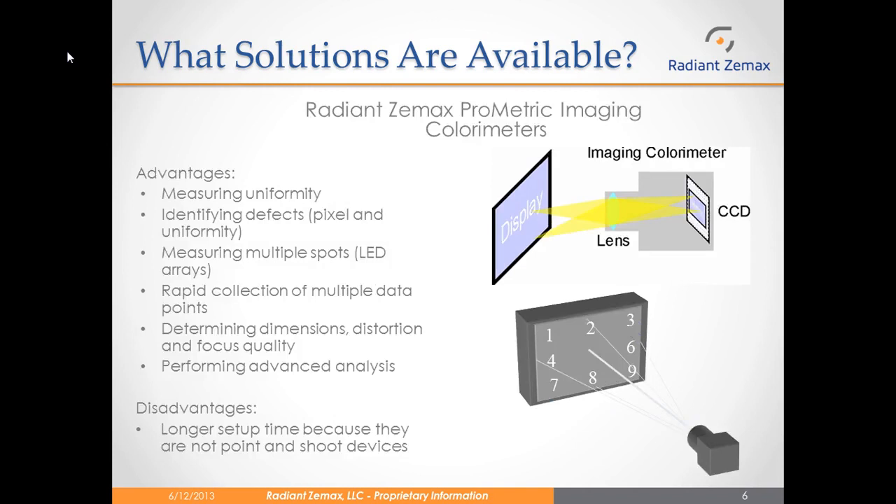Radiant Zemax introduced the Prometric imaging colorimeter lines as a solution for measuring uniformity in brightness and color. Because they are an imaging system, they have an advantage over spot meters because they can measure multiple spots at once through a rapid collection of multiple data points. This allows the Prometric imaging colorimeters to measure for uniformity in brightness and color over the entire display. Also, because of their resolution, they can identify small defects in the device. In the example shown to the right, you place the Prometric imaging camera in front of the device and you can measure all nine points at once instead of having to move the camera nine different times.